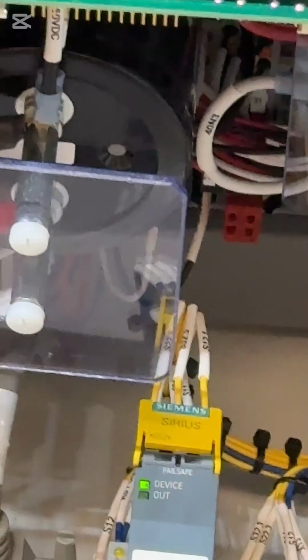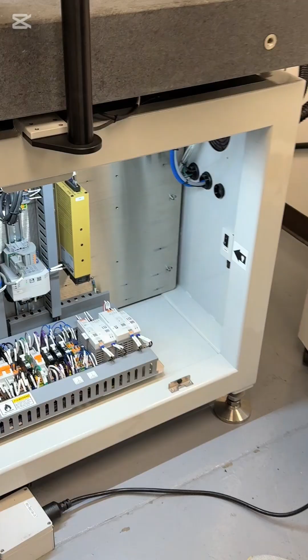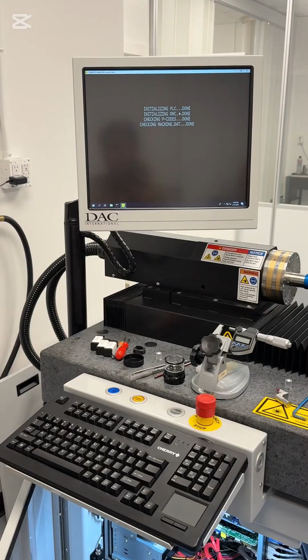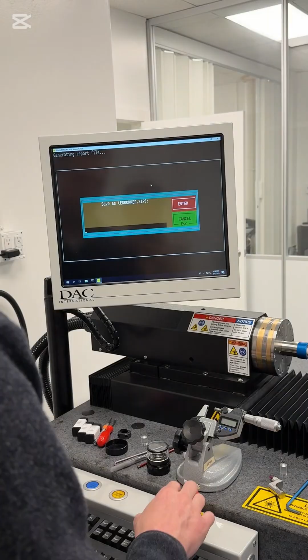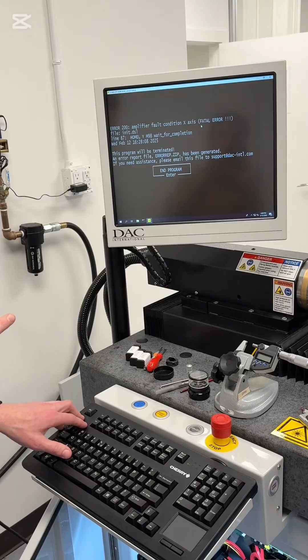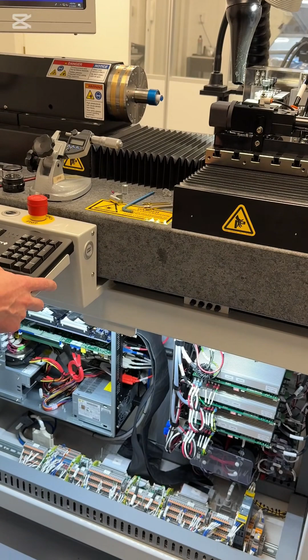Now if we go back to the K1 relay, it's hard to tell, but you can see that the center, there was a button that was kind of up. It's now closed. The relay switched on. So K1's working properly, the amps now have power. So we'll keep moving on here. Okay, that's done. Enter, enter. Amplifier fault x-axis. Okay, enter. We're going to shut down.